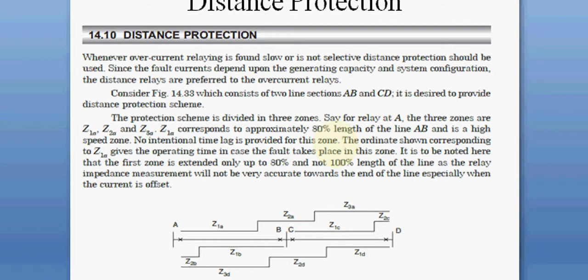The fault current depends upon the system configuration and the generating capacity, so in this case distance relays are preferred over overcurrent relays. It is also found that overcurrent relays are slower and not sensitive in the case of distance protection. In order to remove this inequity we are going to use distance protection.